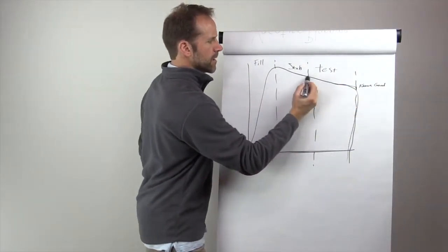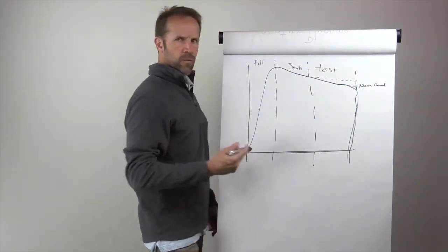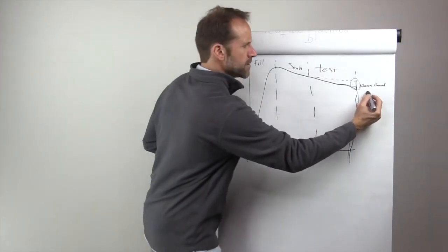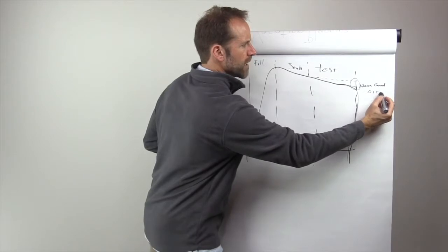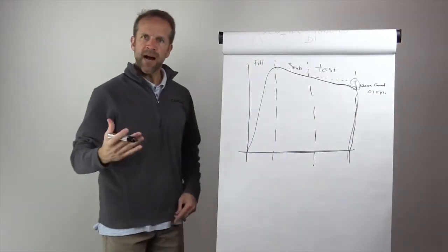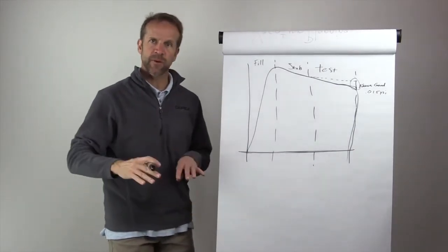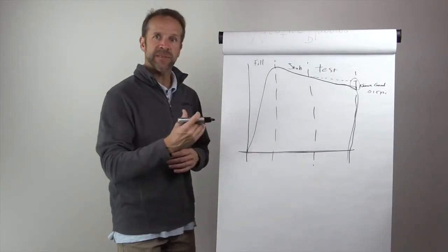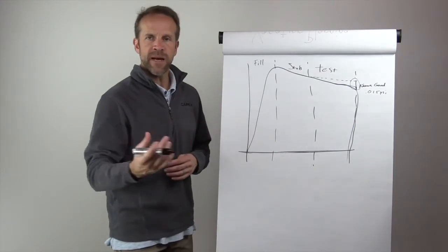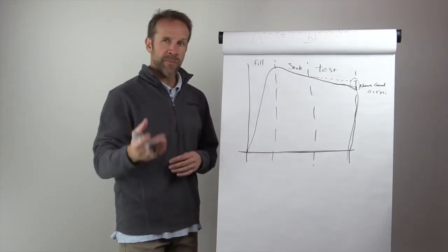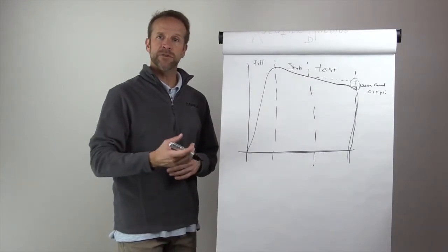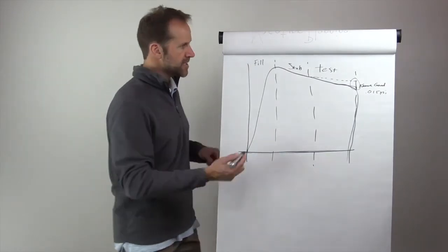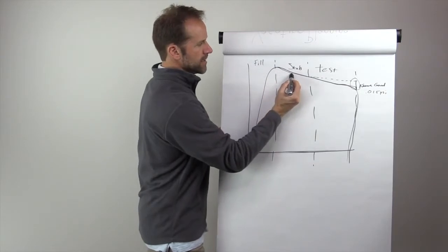So we started our test here, and we're measuring the pressure loss of our known good part through that section. Let's say it lost 0.015 psi. Now we're going to run a second test during the calibration. We let the part relax and come back to a normal state, and then pressurize it again. We run the same test, but this time we introduce the leak standard. So let's imagine we're testing the basketball, and we repressurize it, but now we introduce a known leak. It is a 5 standard cubic centimeter per minute leak at 10 psi. This is what the curve might look like in that scenario.